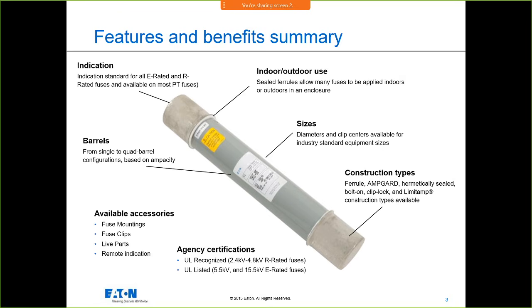They're just bigger. You have, in some cases, indication where you'll know whether or not that fuse has opened. You'll have sometimes a single barrel or up to 4 barrels in one unit. You don't want to be putting these in parallel on your own out in the field. Available accessories, you'll have fuse mounting, fuse clips, and things of that nature. UL recognizes the different types of classes, the voltage class. You have your R-rated and your E-rated. They'll determine the voltage ratings, etc. The fuses, the diameters are in the construction.